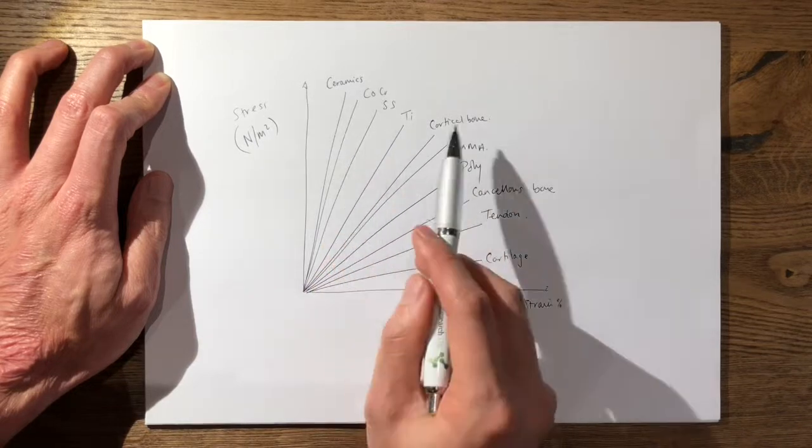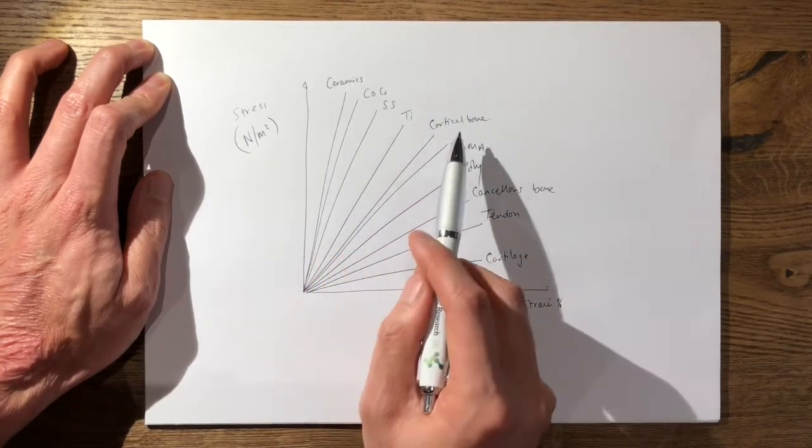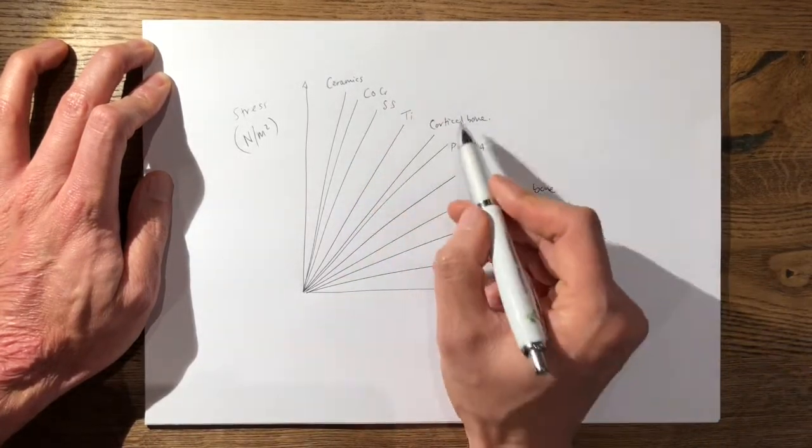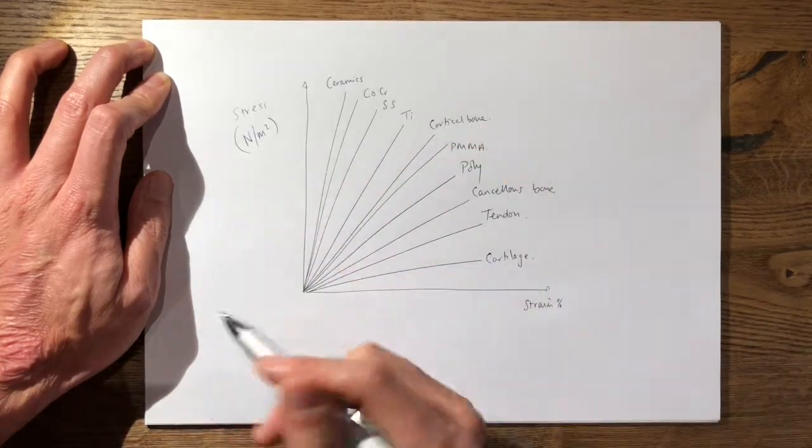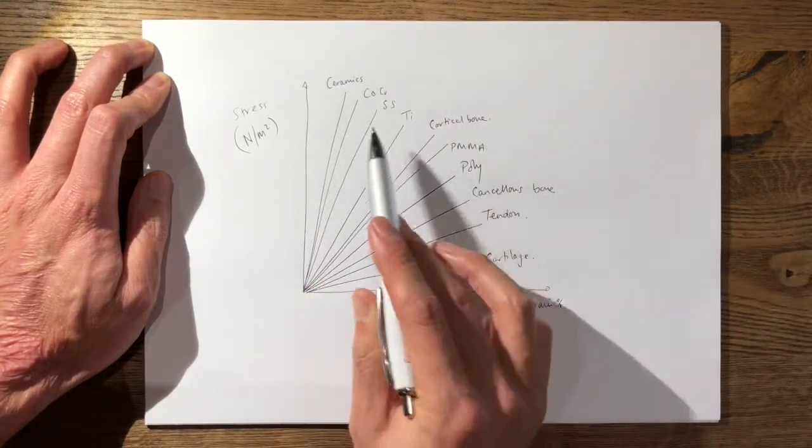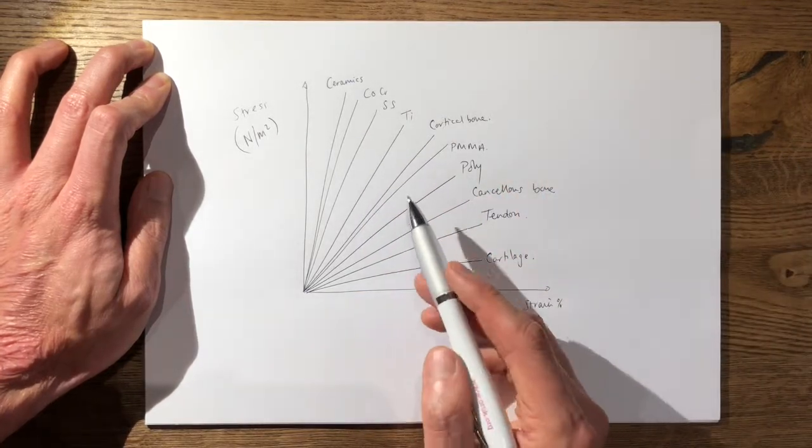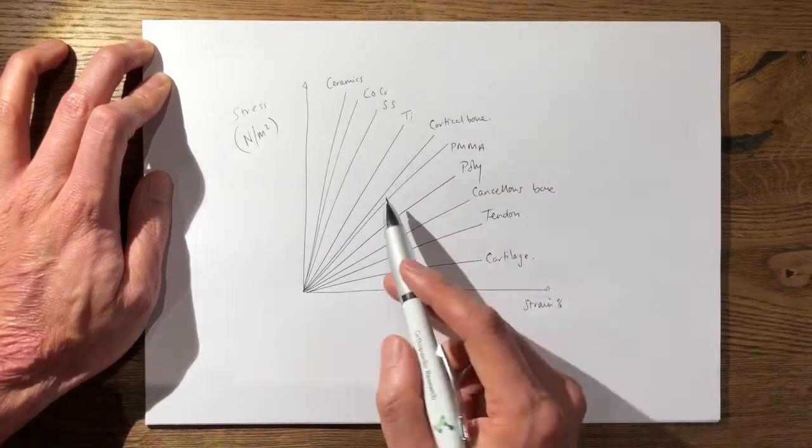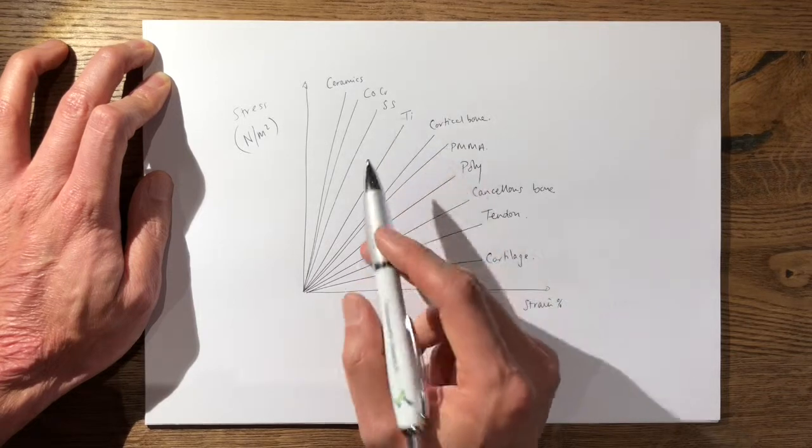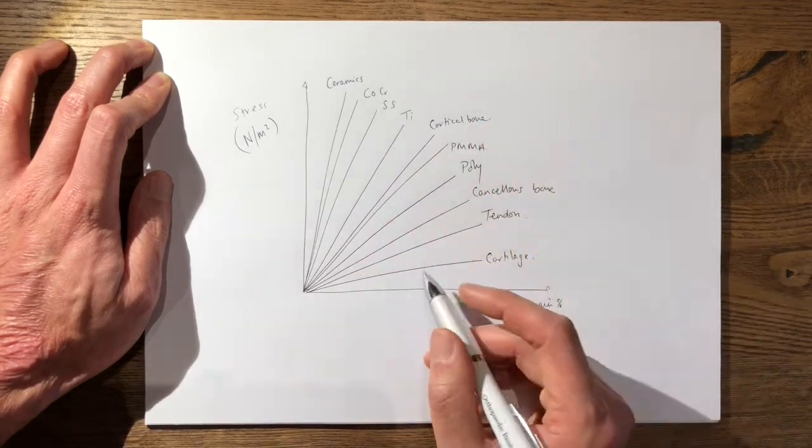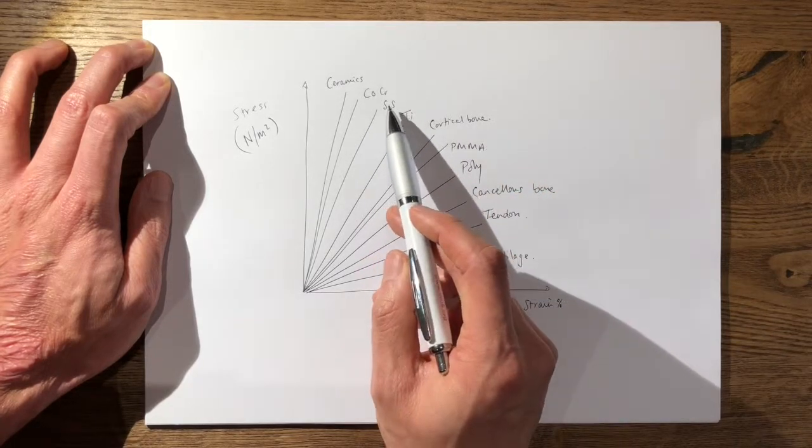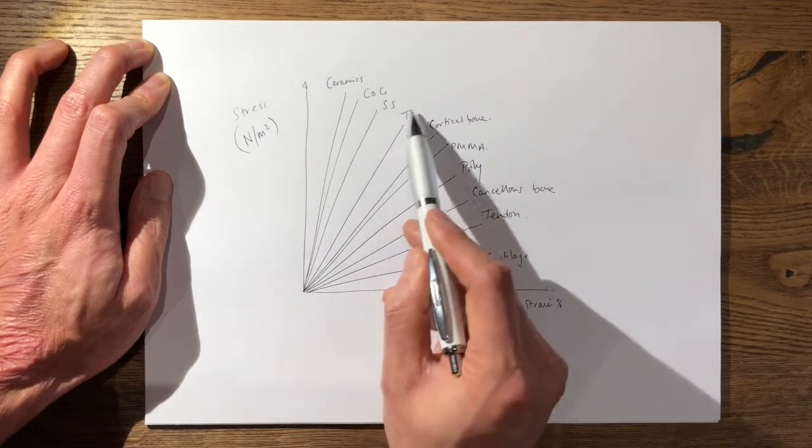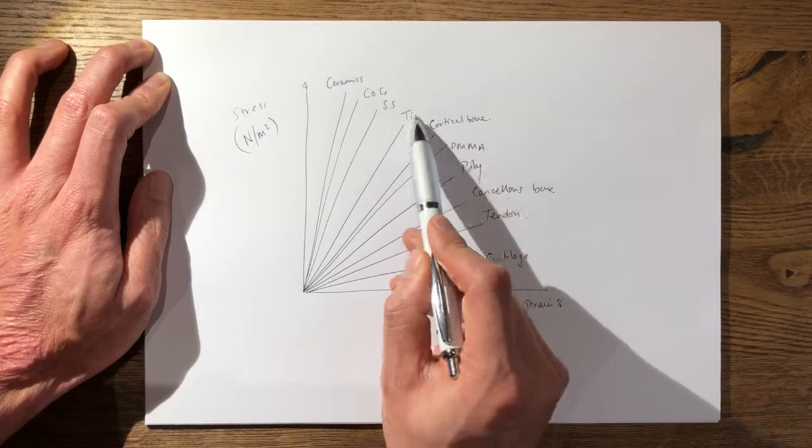Now when you have modulus mismatch, a mismatch in the Young's modulus, you have a stiffer material, so for example stainless steel on cortical bone. The higher the modulus mismatch, the more likely that the stiff material will bear the load of the forces going through the bone. The reason this is important is because if you have that scenario, you'll see stress shielding, which is why you typically get more stress shielding in implants which are stiffer such as stainless steel compared to titanium, which has less of a modulus mismatch.